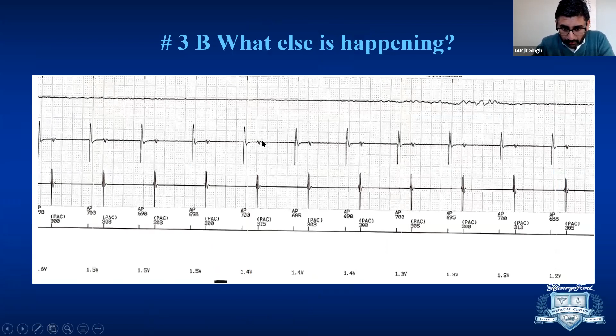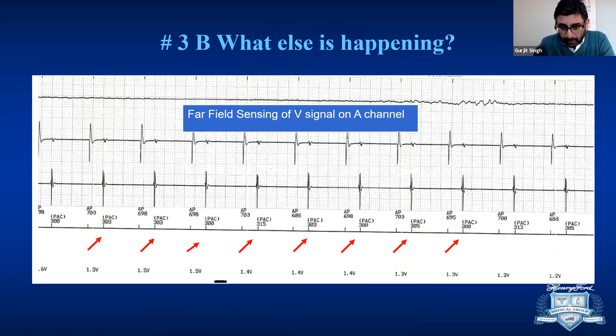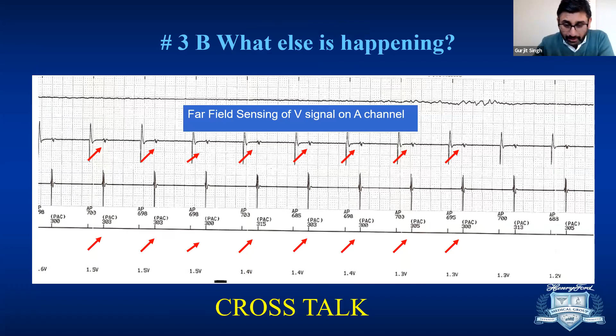And the third one, as everybody has picked it up, is the far field signal seen on the atrial channel here. Okay, and that's far field signal. It's called crosstalk. All righty. Now, why that happens, as Dr. Upadhyay explained last time, is shown in this X-ray, where the atrial lead is sitting in the appendage. So normally we try to put the leads in the appendage, right?